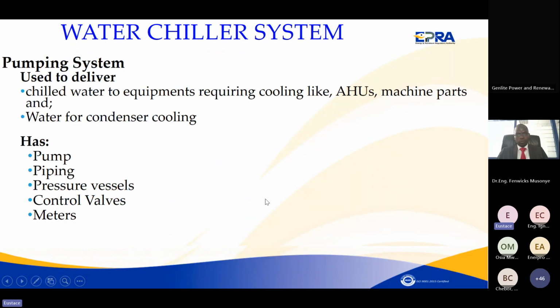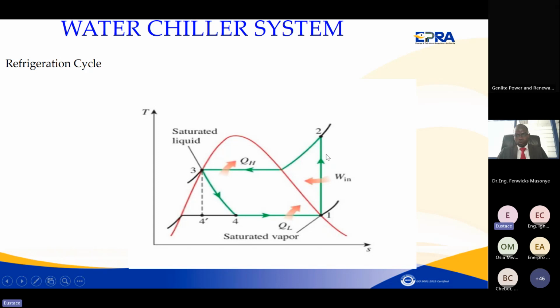In a TS diagram, you can see the lower part, which is normally called the low pressure, low temperature part, where you absorb heat from a cooled space. Like in your refrigerator, that's where you put your drinks or food to be cooled. Then the refrigerant goes to the compressor, where you add work. It is in the compressor that you add energy to the refrigeration cycle. This is where we want to minimize the work or the power going into the refrigeration cycle as much as possible. That is enabled by ensuring that the heat transfer surfaces are able to absorb as much heat as possible. So you have to make sure that the heat transfer surfaces of the evaporators are as good as possible.